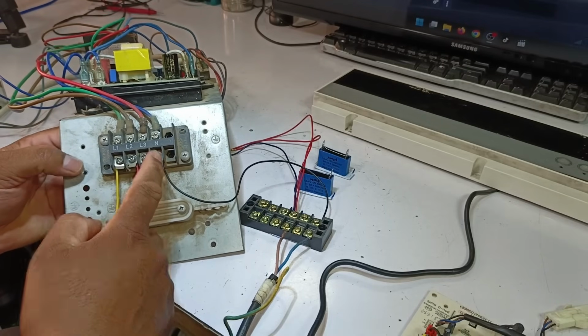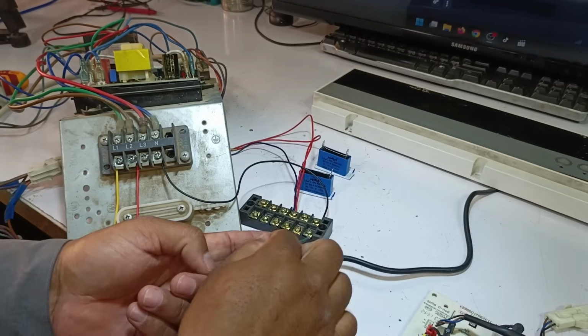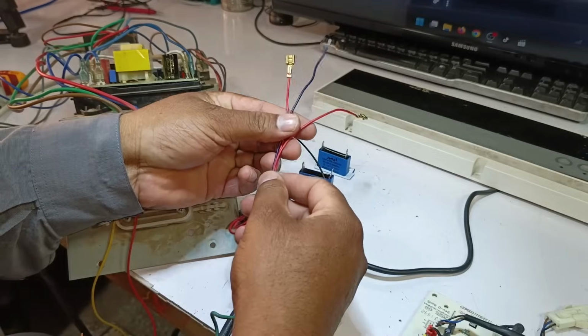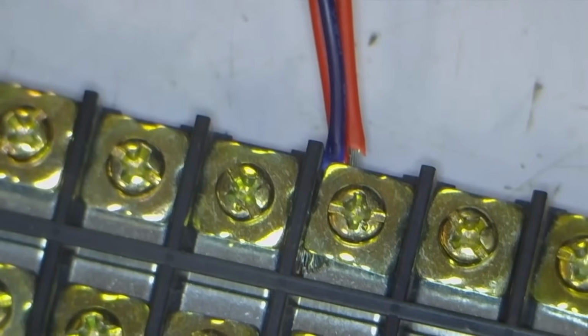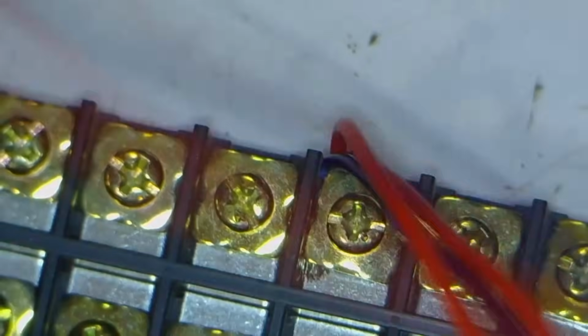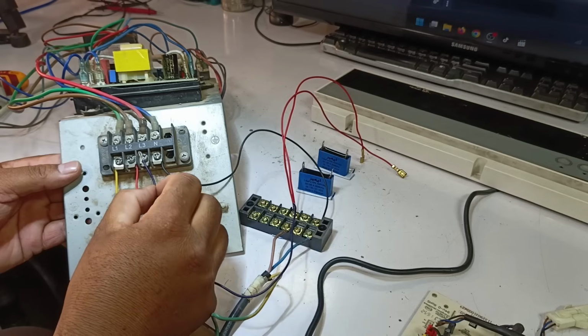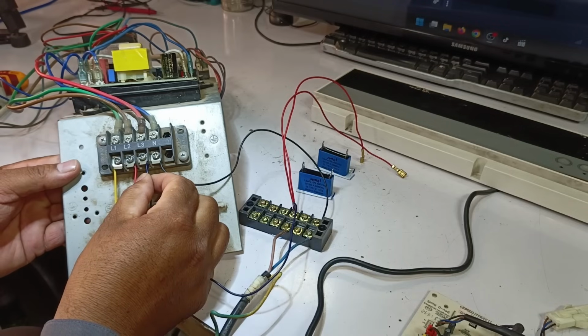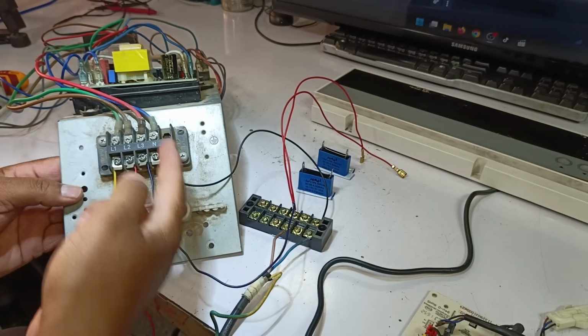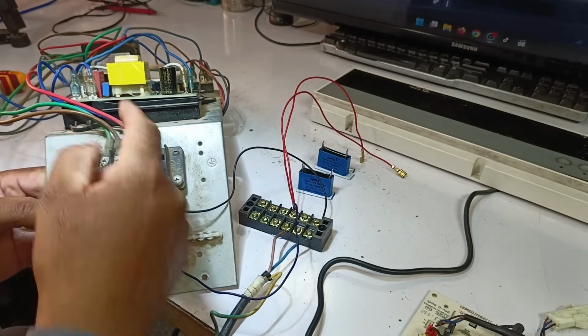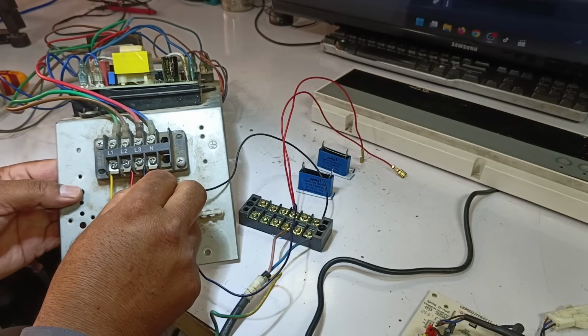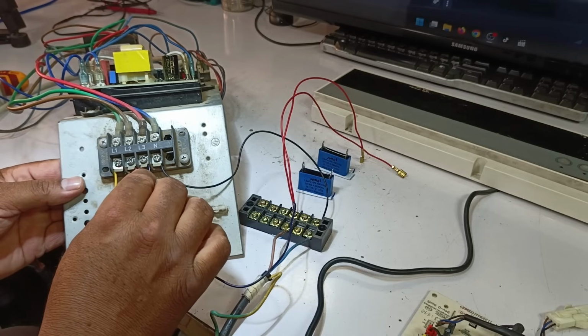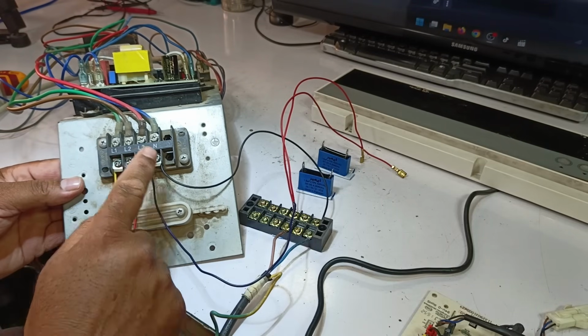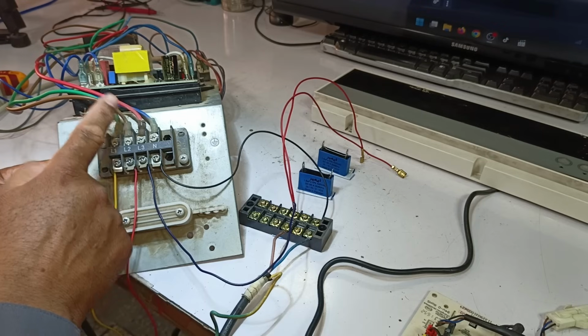Now, we need to make the connection for line 3. You might remember that along with the main single-phase line, we had created 3 connections, 2 red wires and 1 purple wire. Now, we will take the purple wire and connect it to line 3. This connection is very important because it acts as the main supply that powers the outdoor circuit board. It's crucial that you do not mix up these connections. The phase we are connecting now, L3, is the actual main operating supply for the PCB.